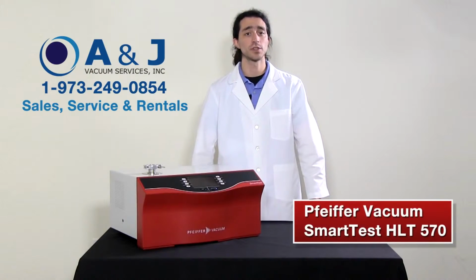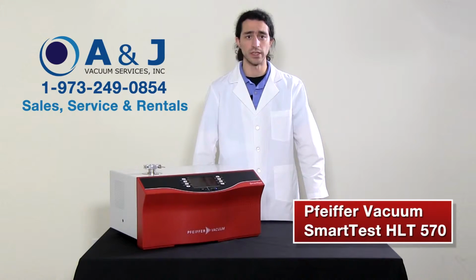When searching for leaks with the Smart Test, the test gas entering or escaping through leaks in the sample is detected. For gas to flow through a leak, a pressure difference between the inside and outside of the sample is necessary. For this, either excess pressure or vacuum pressure is generated inside the sample.